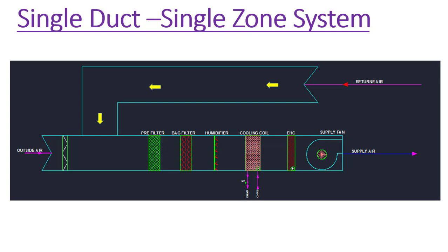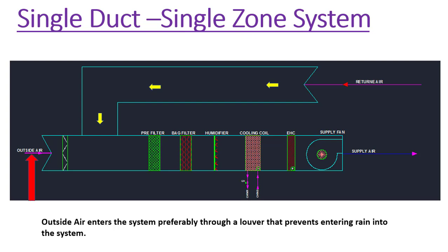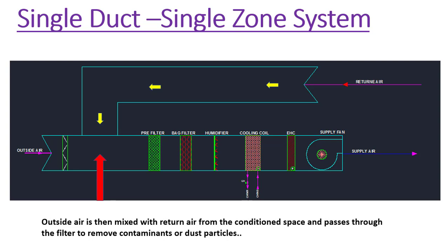For simplicity, we will explore an example of a single duct single zone system. This diagram shows a recirculating type AHU serving a single zone with a single supply duct. Let's look at each component one by one. Outside air enters the system preferably through a louver that prevents rain from entering. This outside air is then mixed with return air from the conditioned space and passes through a filter to remove contaminants and dust particles.